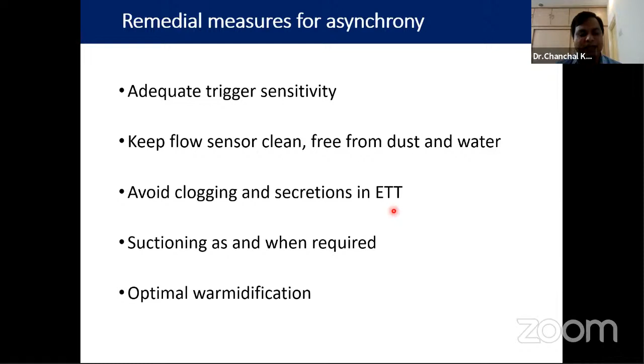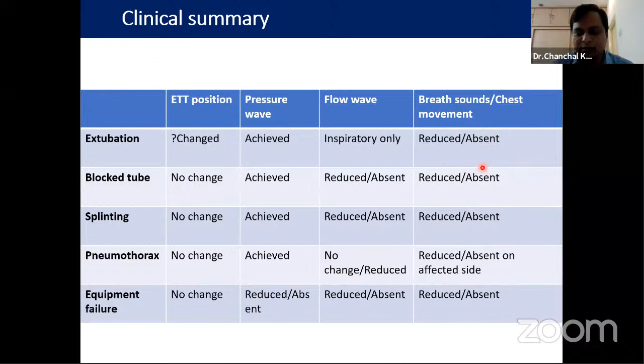So in summary, we may find that the endotracheal tube position will be changed in case of extubation, but will be unchanged in other conditions. The pressure waveform will be regular in most of the conditions except for equipment failure, where one may find a reduced pressure waveform. The flow waveform will show only an inspiratory pattern in case of extubation, but in most of the other conditions, the flow waveform will be reduced. And in auscultatory findings, one may find reduced or absent breath sounds in most of the conditions.